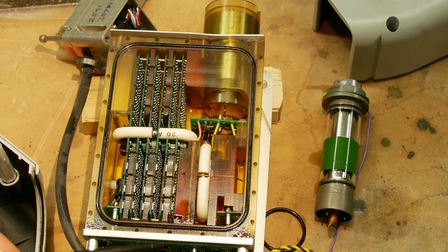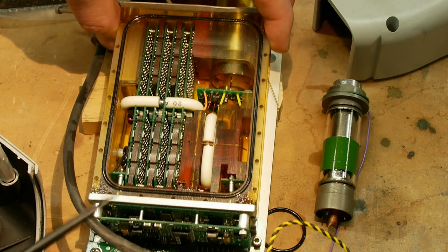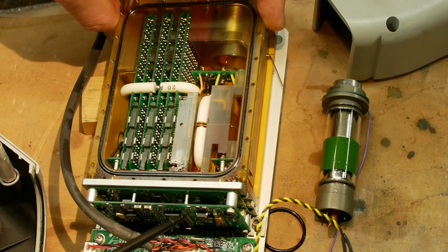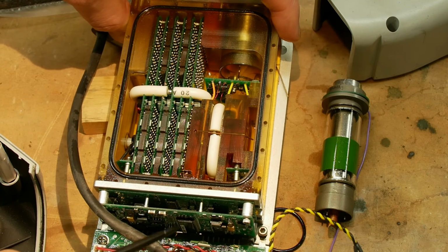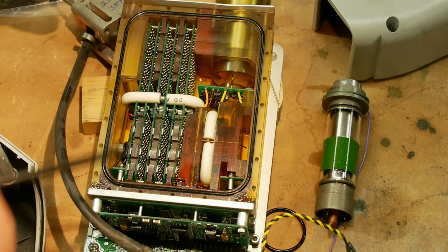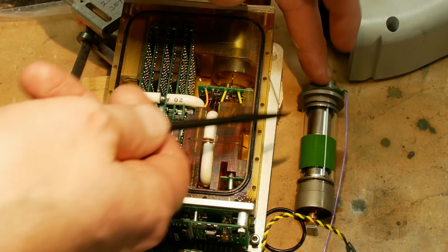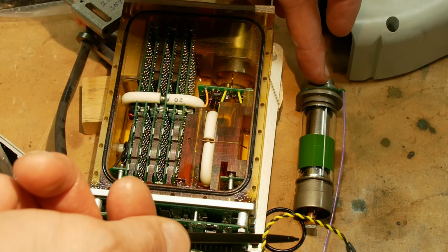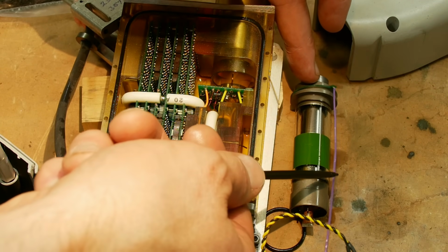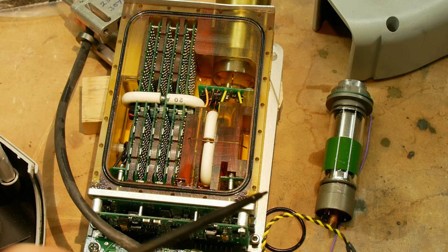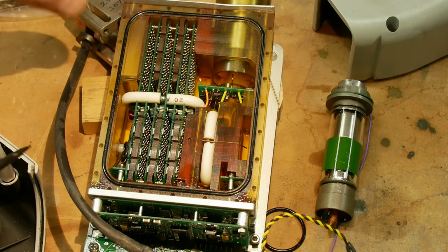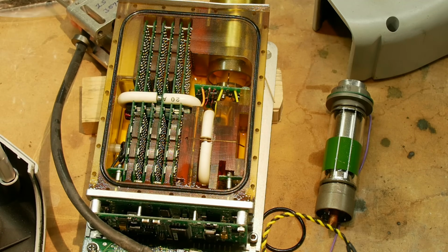There's a couple other circuit boards outside the high voltage that probably do some of the filament monitoring. So there's potentially a way that this thing measures the amount of current going through the tube. It's probably this little purple wire that goes all the way back. So basically, sense this wire, and when it gets up to 7 microamps, cut off the filament control voltage. And if it drops below 7 microamps, give it some more filament current, and that's how it regulates itself.